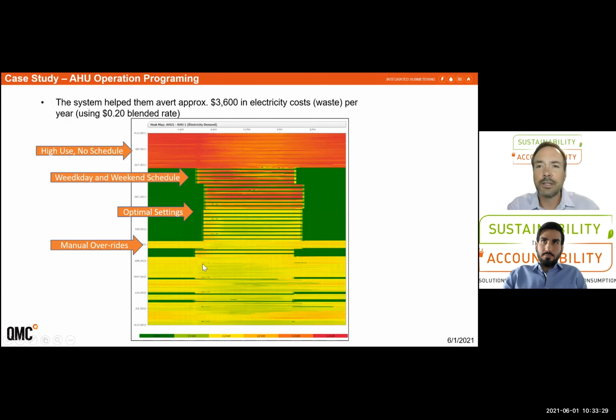So I wanted to take a look at a few examples here of specific case studies we've done. This is one of my favorites. It was one of the first ones I did with a LEED project where we were working with an M&E consultant, and they deployed our meter system, and we're looking at the data and seeing that the consumption in this building was not matching what the modeling had done. So we worked with them to develop a graph after a few months, and showed that this air handling unit was essentially running at full tilt 24/7. And you can see through this heat map it was using a lot of energy over this period.